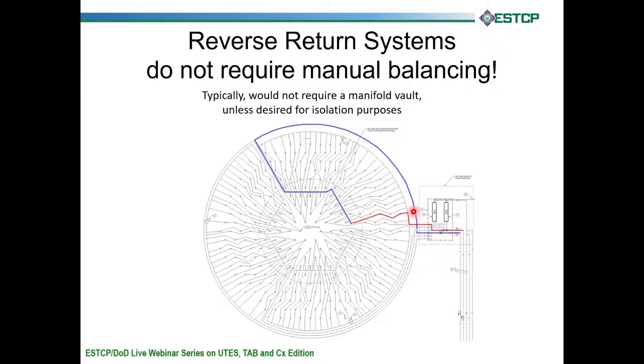In the same way, the second sub-circuit would be the second one to come off of the supply main, but it's the second from the last to hit the return main. So essentially what you end up with is each one of these sub-circuits has the exact same length of pipe and is the exact same distance away from the pump. So typically the circuits that are closer to the pump get the most flow, and the ones that are farthest away from the pump get the least flow. With this configuration, each circuit is the same distance away from the pump and has very close to the same pressure drop. Each circuit has the same pressure drop overall, pretty much.